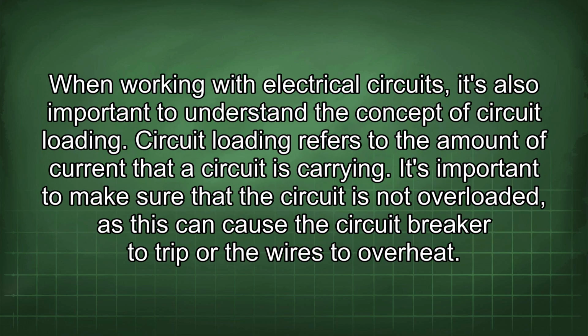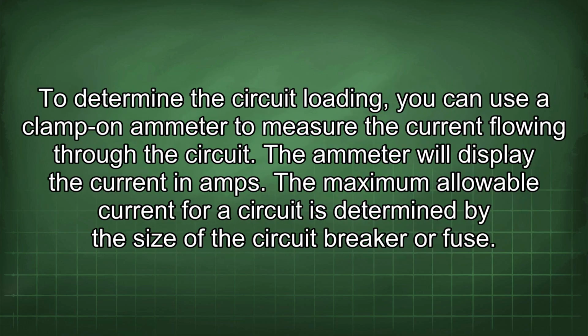When working with electrical circuits, it's also important to understand the concept of circuit loading. Circuit loading refers to the amount of current that the circuit is carrying. It's important to make sure that the circuit is not overloaded, as this can cause the circuit breaker to trip or the wires to overheat. To determine the circuit loading, you can use a clamp-on ammeter to measure the current flowing through the circuit. The ammeter will display the current in amps.